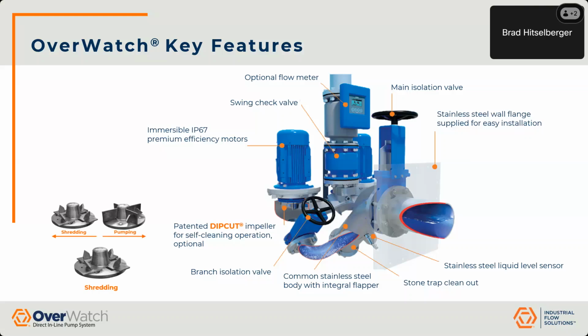So this is a really unique impeller that is really cool. You can see this on the left. We'll highlight some of the different impeller options after this, but it has the option to go forward and reverse based on the controls. So when it's going forward, it's going to be pumping like the picture in the top right, and then it's going to flap down and go into reverse and become a shredder. So it's a vortex style impeller. It's going to be very good for passing suspended solids, but if you need to react without sending any human intervention out there, it's going to be able to shred anything that comes up towards it. So you can see the picture, the animation going forward and backwards.